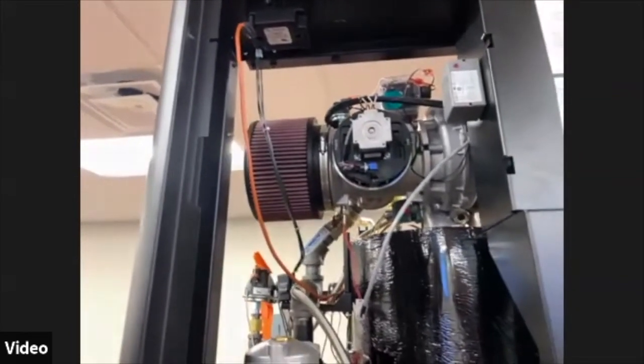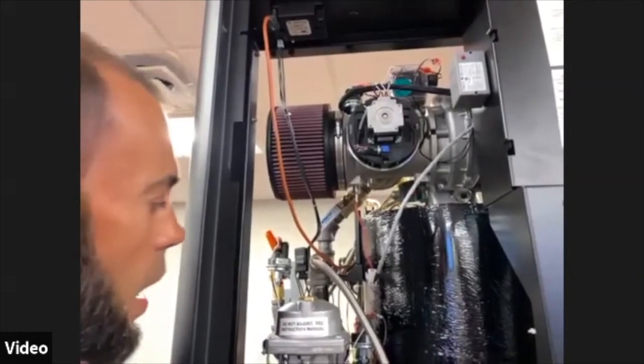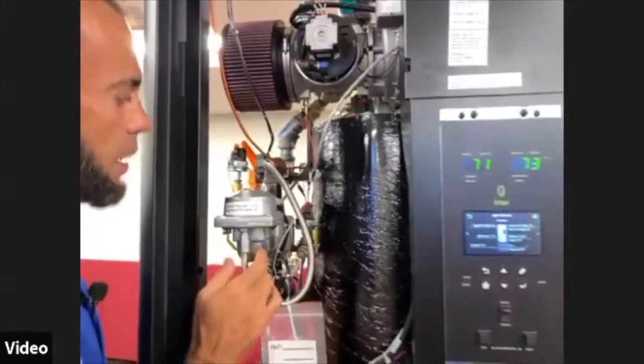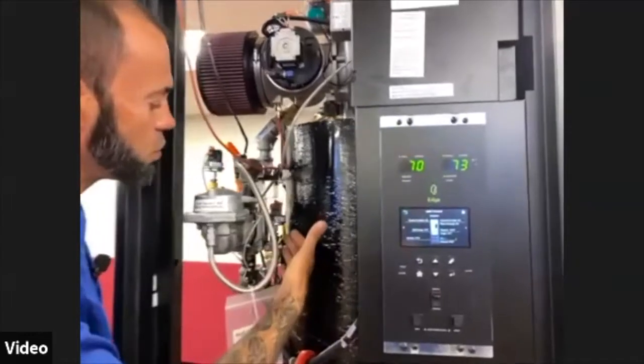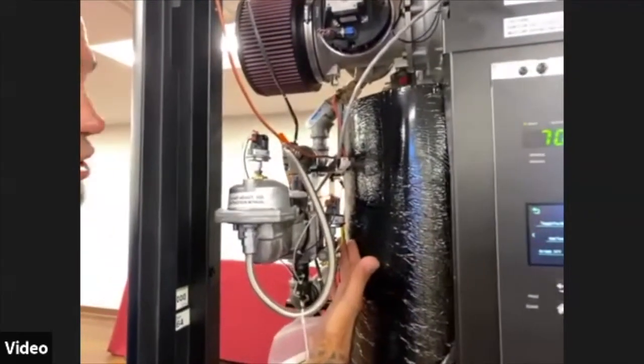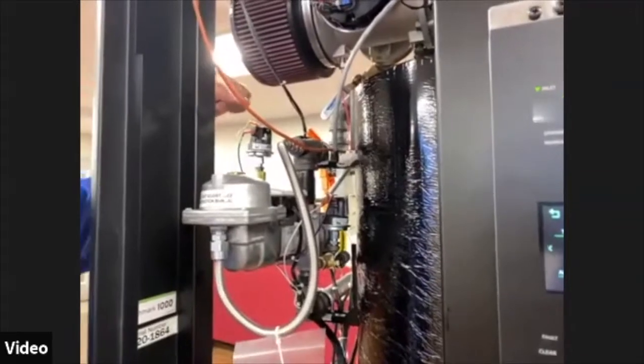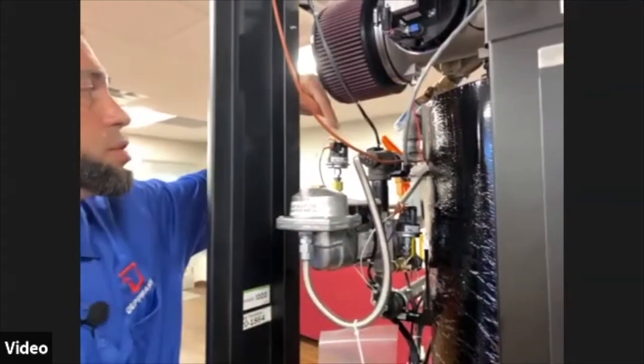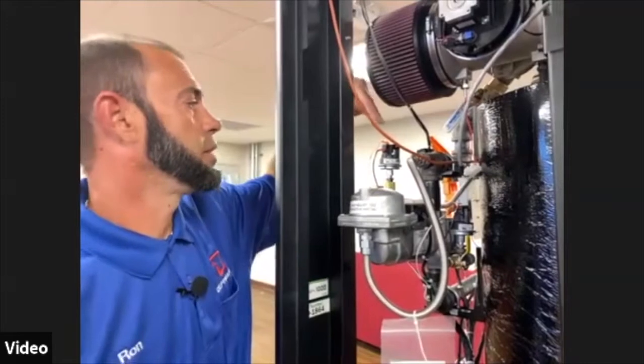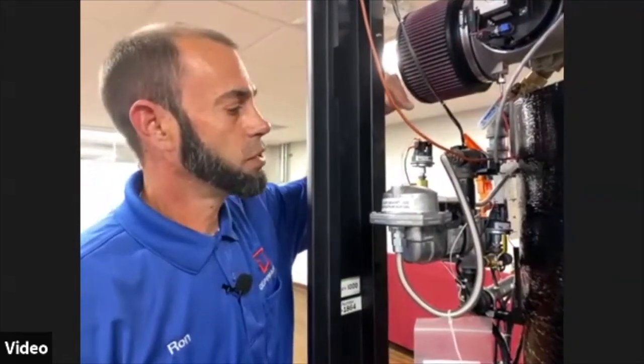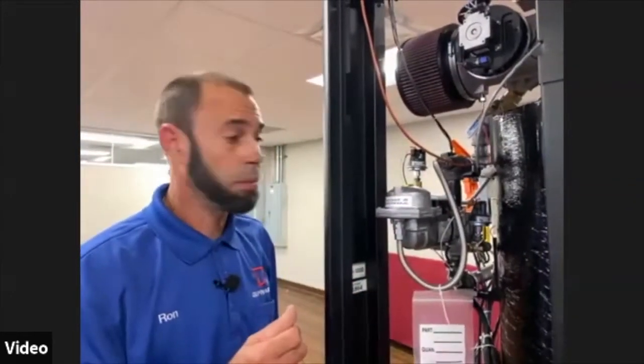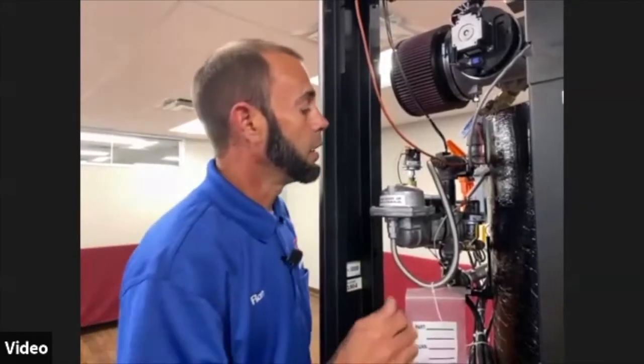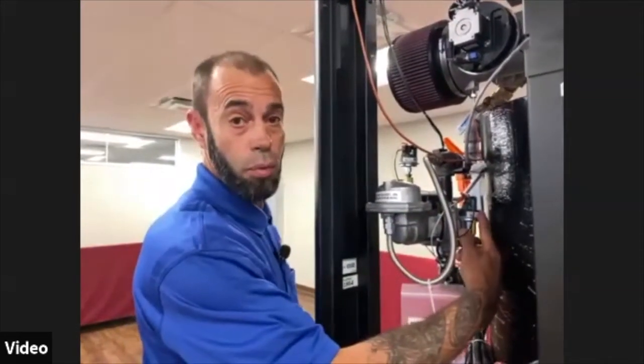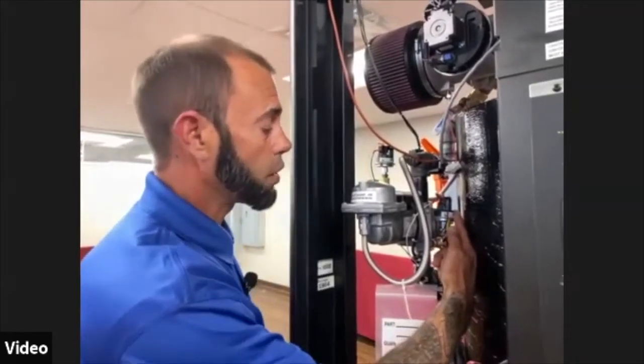This is our safety shutoff valve or our gas valve. The safety shutoff valve also contains gas pressure switches, which will be the low gas pressure switch, and over here is a high gas pressure switch. These both have factory settings as well, and they're sealed, so please do not adjust them. If they're out of range, the best thing to do is replace them, or if they fail, just replace it. This, I believe, is set for 2.6 inches water column.